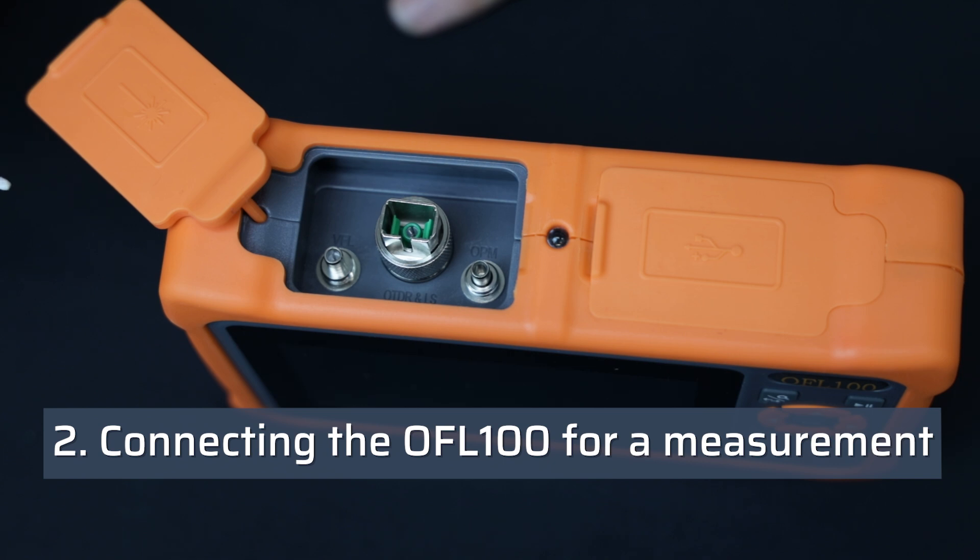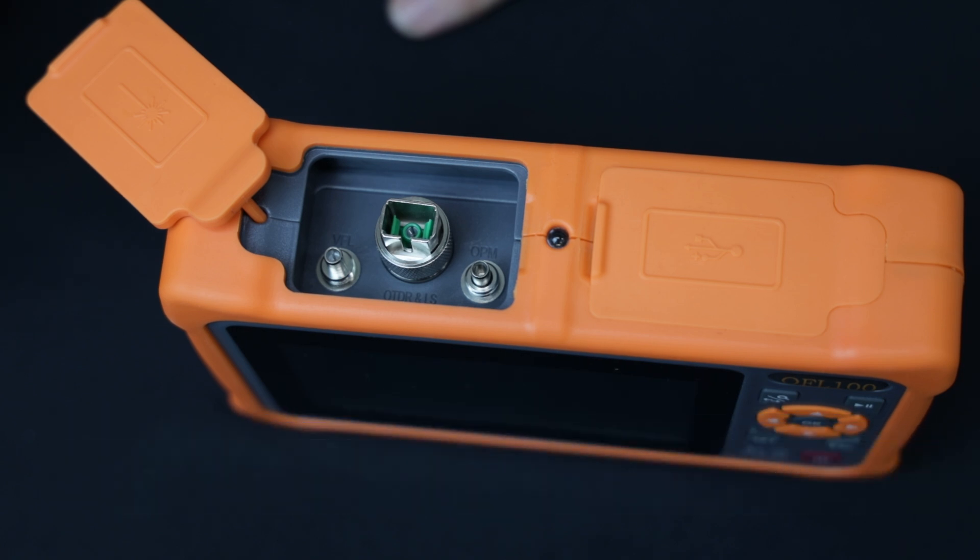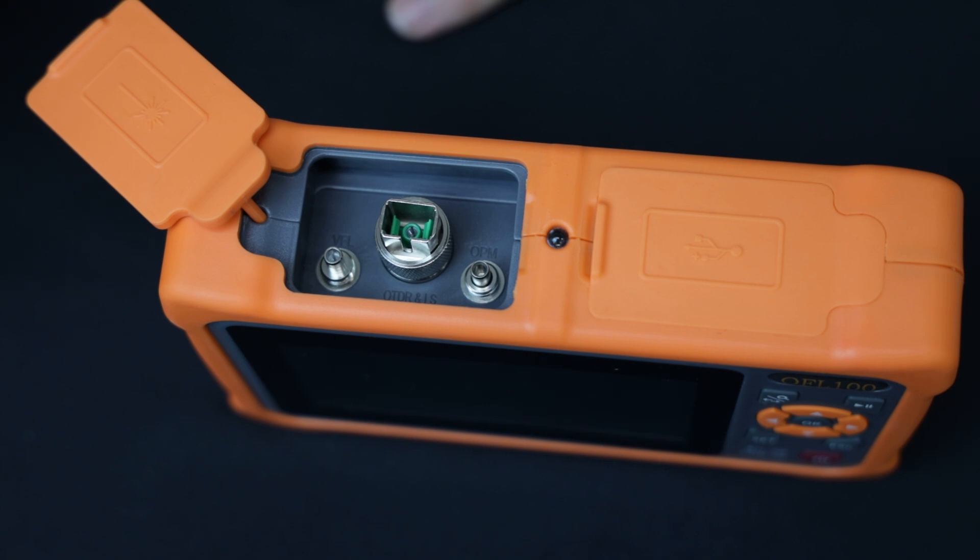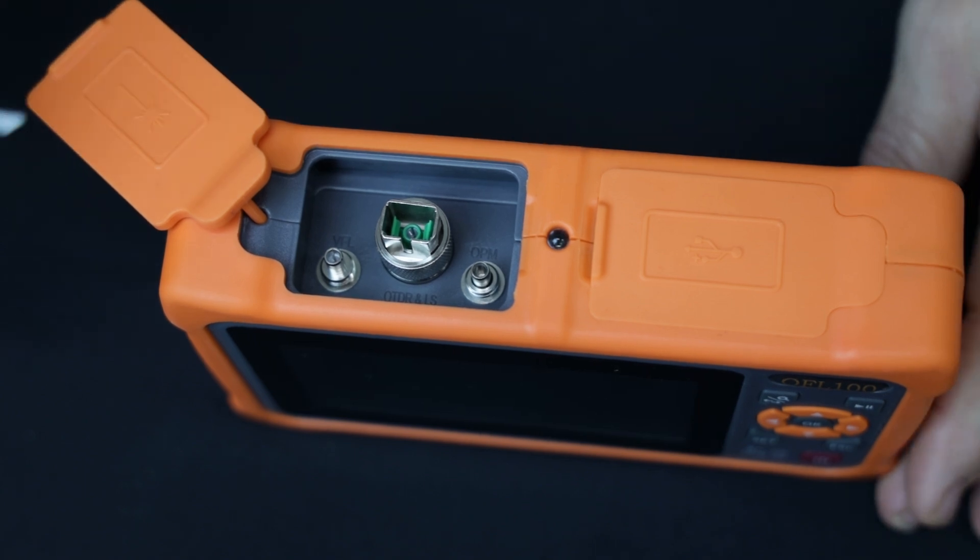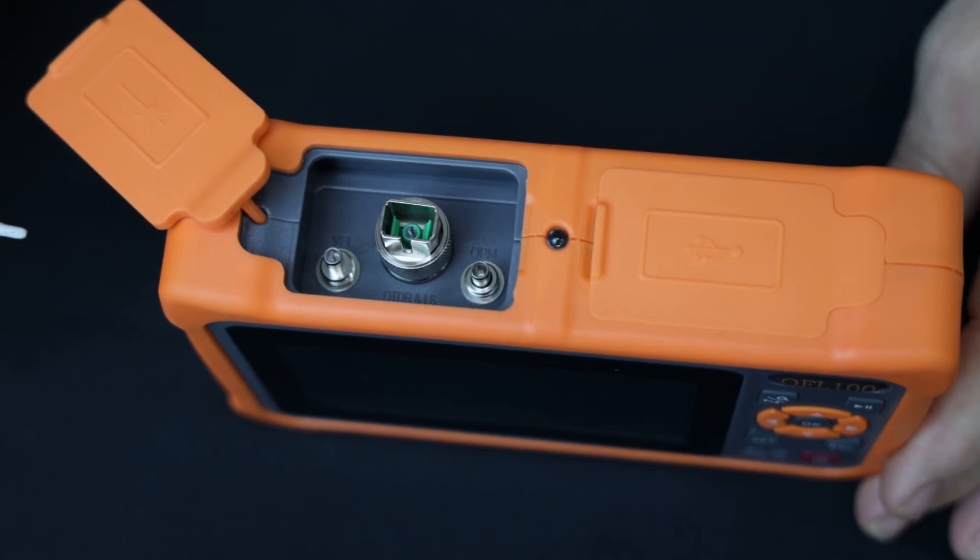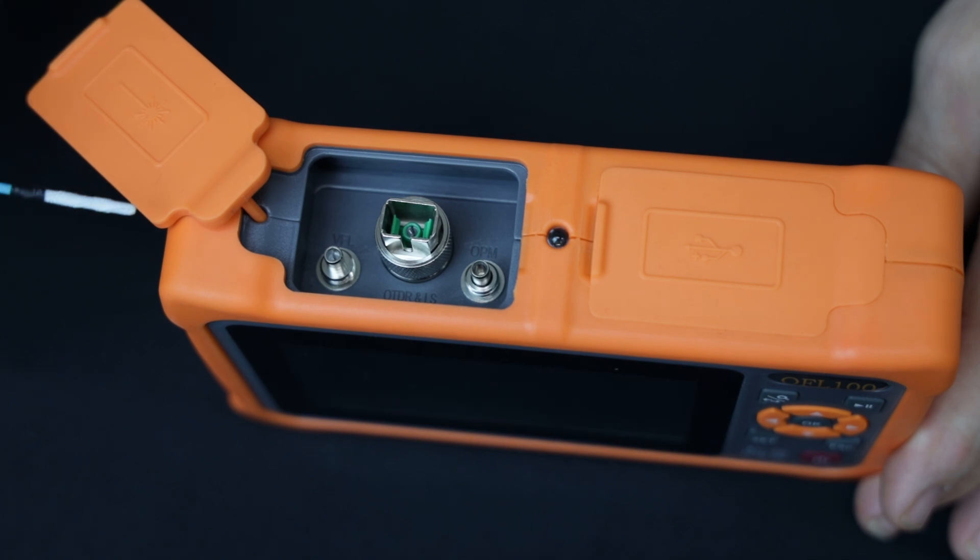More than 80% of all failures in fiber optics is due to not cleaning or improper cleaning. This also pertains to the connections made during testing procedures. If proper cleaning is not performed, the OTDR bulkhead will be damaged very quickly and will require repair or replacement. Damaged and contaminated connectors will cause high insertion losses and high reflections.